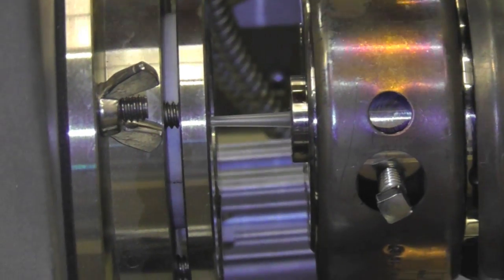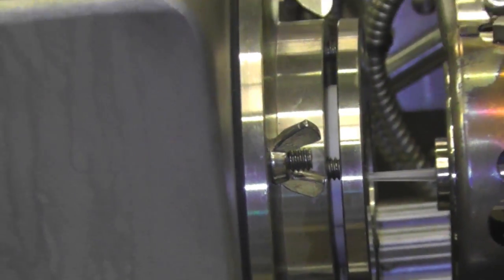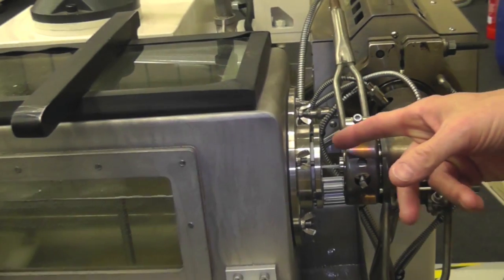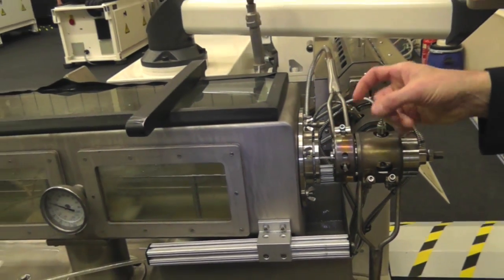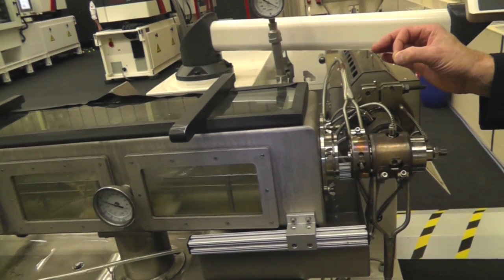My name is Bob Bessemer, I'm the downstream sales manager for medical extrusion at Conair. Today we're showing you a small medical micro-bore line where we're making taper tubing. We're using the vacuum to create a differential in the tank, using just enough vacuum differential pressure to hold the water so it doesn't pour out, so we can critically control the concentricity.